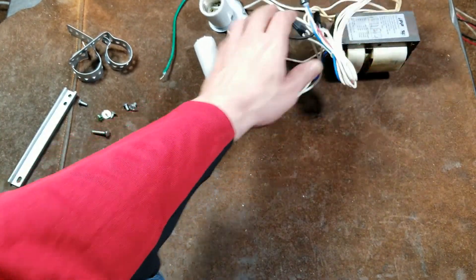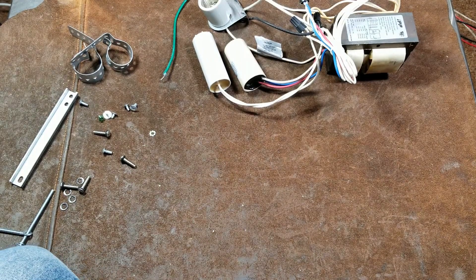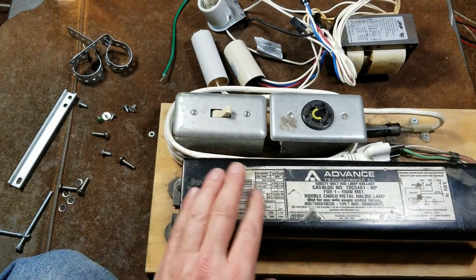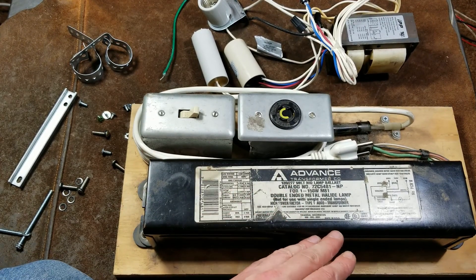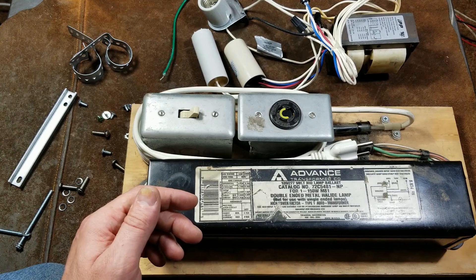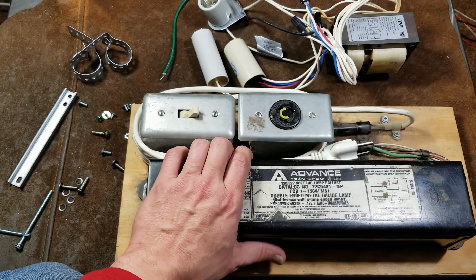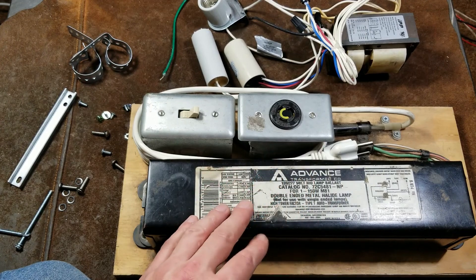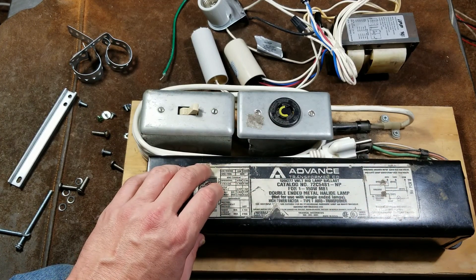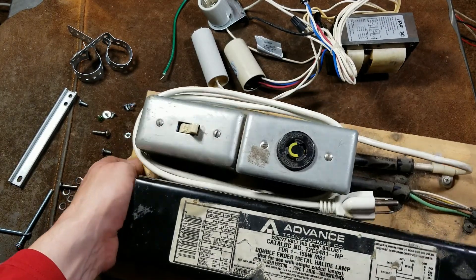If you replace the bulb on time, many of these ballasts will just last decades. A much more premium example is this American-made Philips Advance ballast for a double-ended metal halide. It's an all-integrated unit — thermally protected, completely potted — just a nice sealed, very long-lasting assembly. Philips Advance are known as some of the best ballasts, as well as power supplies for LEDs. It's surprising to see how far the Hubbell has fallen compared to Philips.